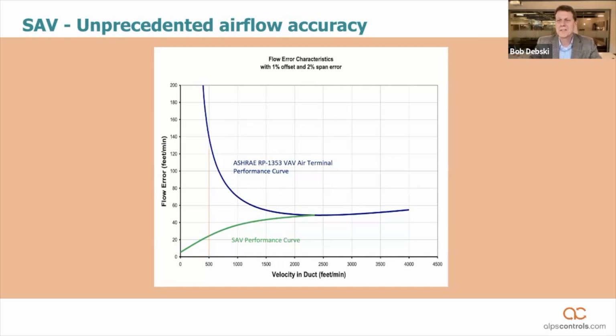So let's introduce the smart air valve, which provides unprecedented airflow accuracy. Here's that same graph we looked at previously from the research project from ASHRAE. Same curve in blue, but overlaid on that curve is the performance of the smart air valve. And what you'll see is that the accuracy of the smart air valve actually increases as the airflow decreases, totally opposite of the current technologies that exist. And this is what's going to have such a big impact on the marketplace.